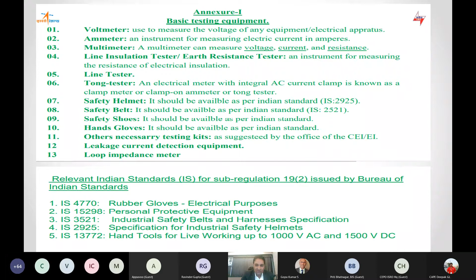Relevant IS sub-regulation 19(2) is issued by the BIS. Rubber gloves are specified in IS 4770, PPE in IS 15298, industrial safety belt in IS 3521, industrial safety helmet specification in IS 2925, and hand tools for live working up to 1000 V AC and 1500 V DC are given in IS 13772.